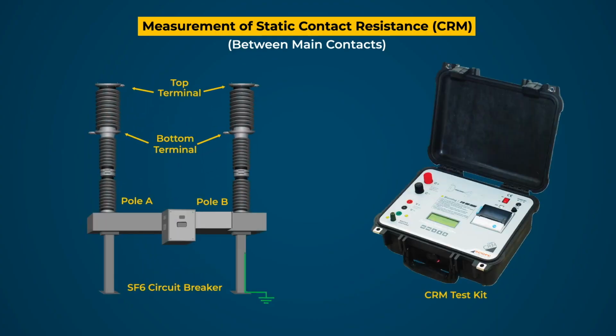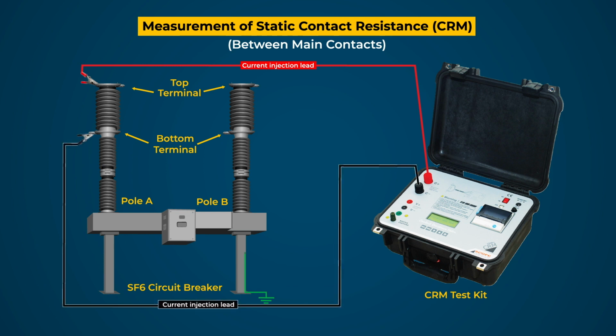Here we are testing pole A of a breaker. First, open the connections of both end terminal connectors. Close the main contacts of the breaker under test if they are open. Connect the positive current lead of the test kit to the top terminal of breaker pole A and connect the negative current lead of the test kit to the bottom terminal of breaker pole A.